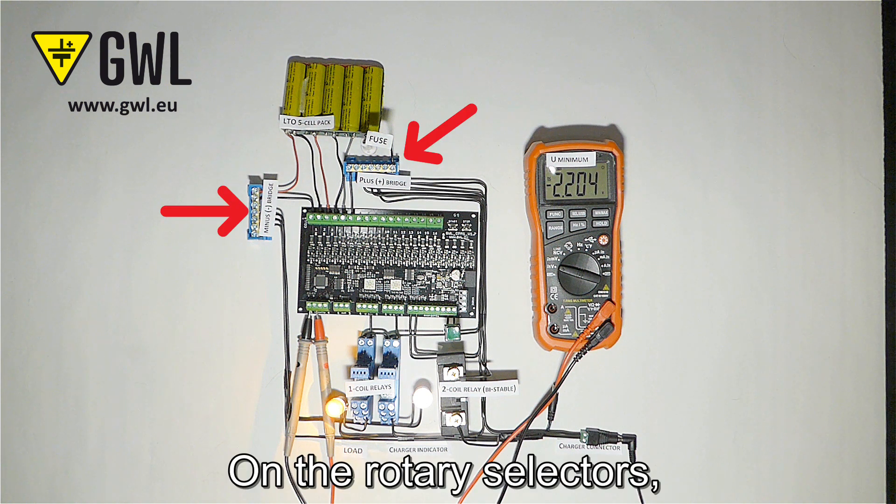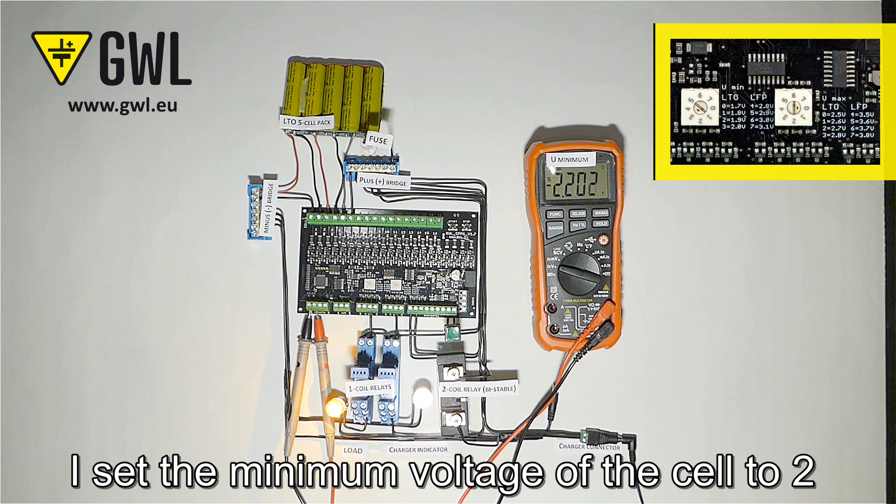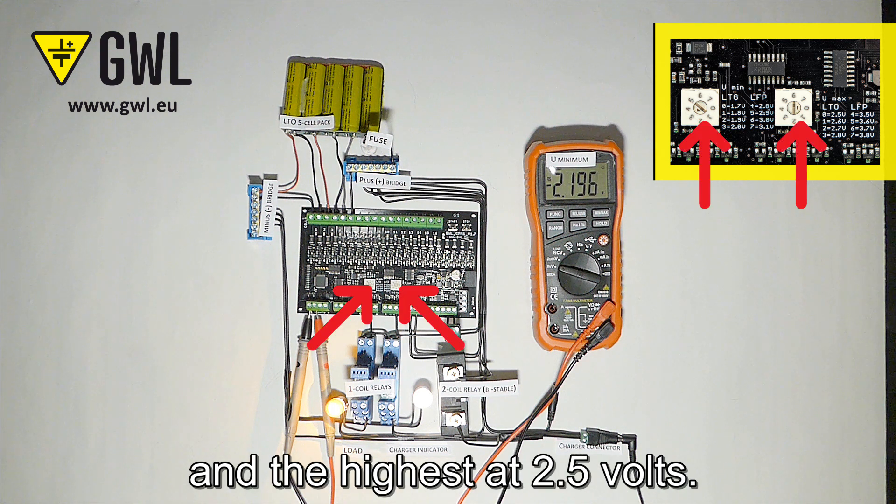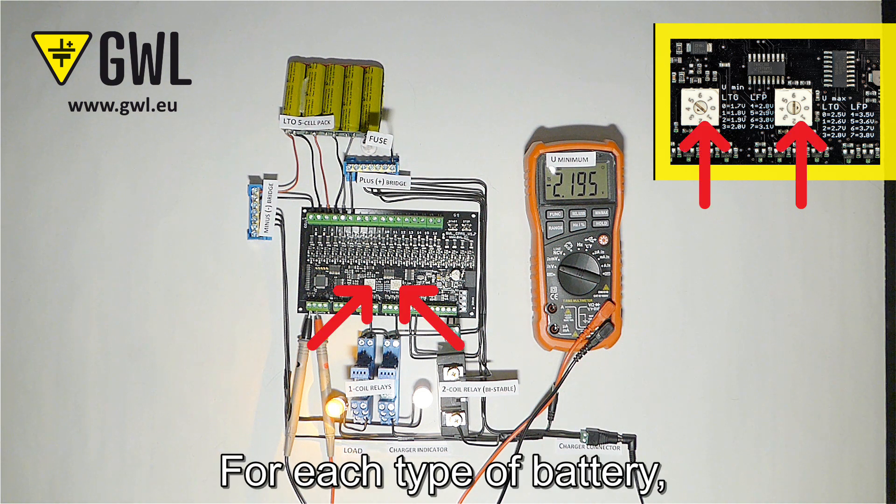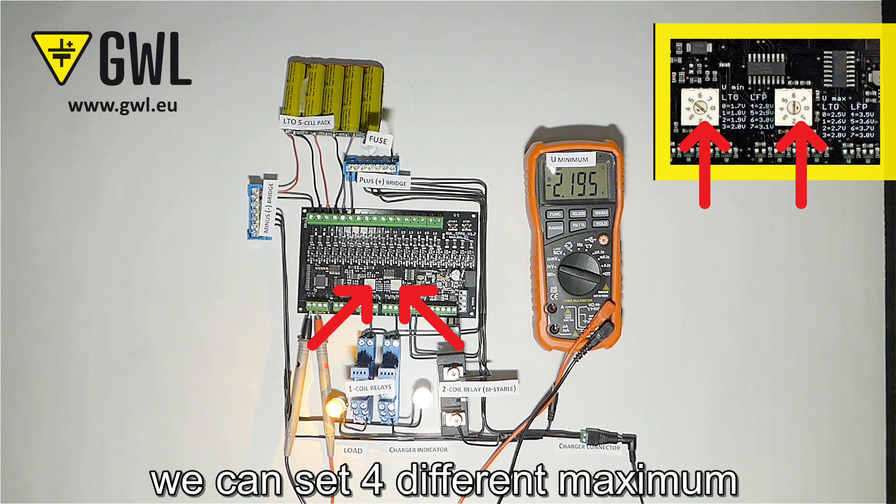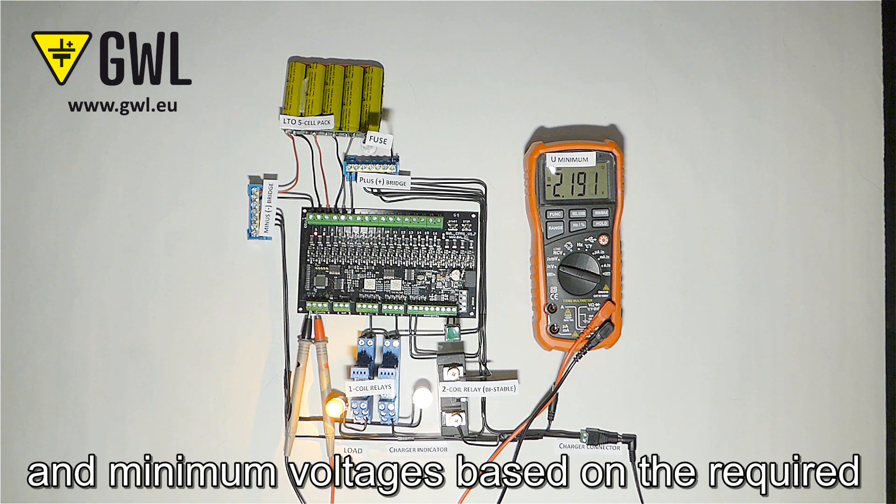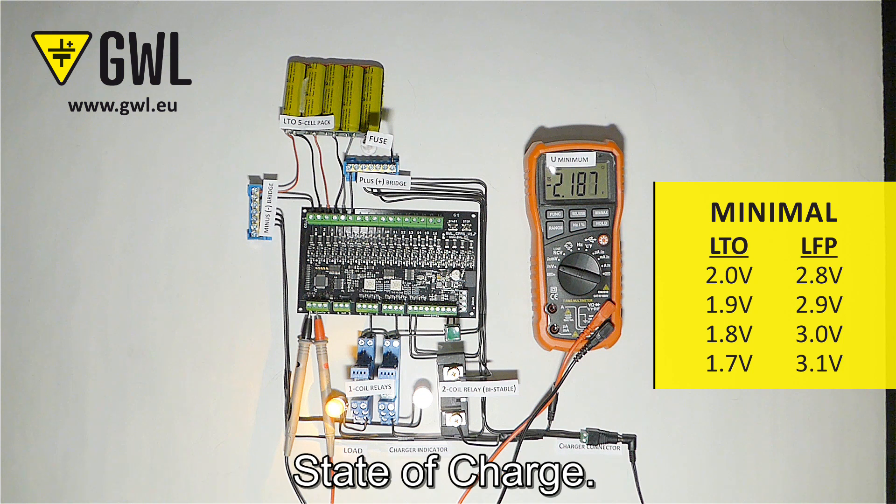On the rotary selectors I set the minimum voltage of the cell to 2 and the highest at 2.5 volts. For each type of battery we can set four different maximum and minimum voltages based on the required state of charge.